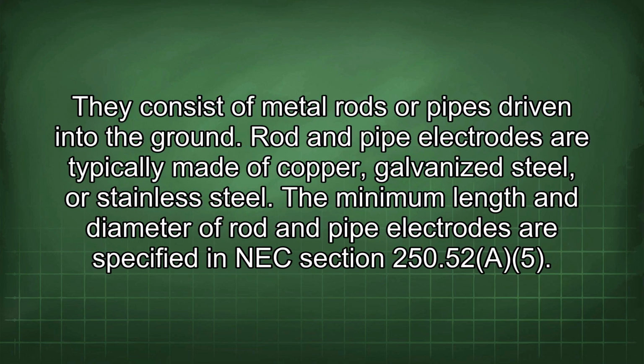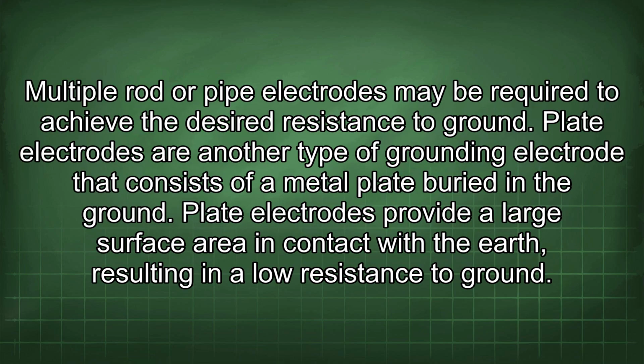Rod and pipe electrodes are the most common type of grounding electrode. They consist of metal rods or pipes driven into the ground. Rod and pipe electrodes are typically made of copper, galvanized steel, or stainless steel. The minimum length and diameter of rod and pipe electrodes are specified in NEC Section 250.52. Multiple rod or pipe electrodes may be required to achieve the desired resistance to ground.